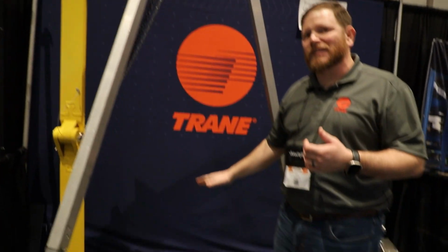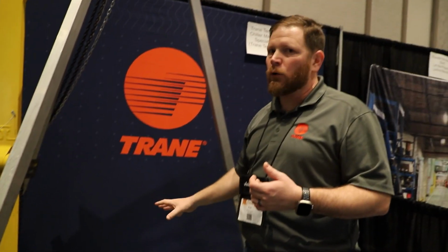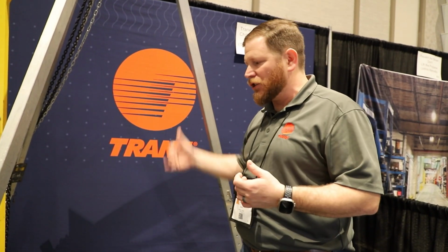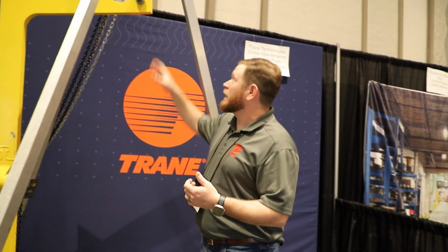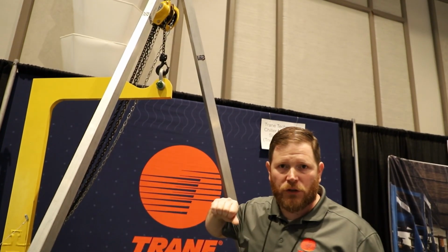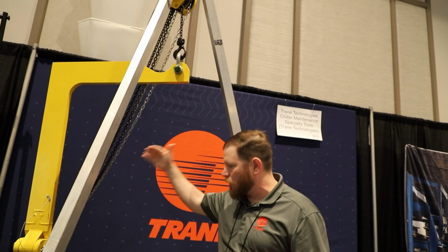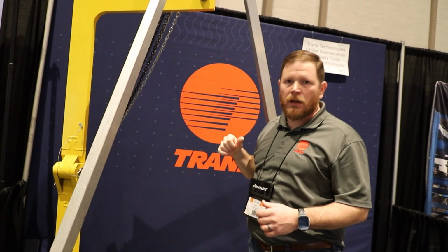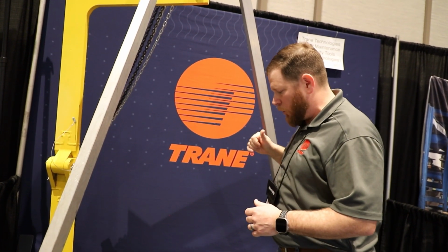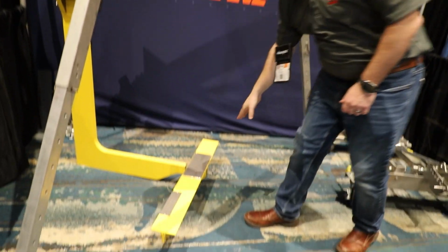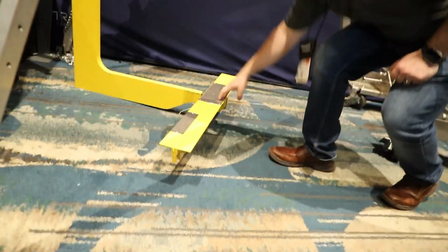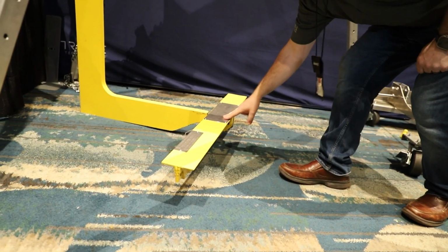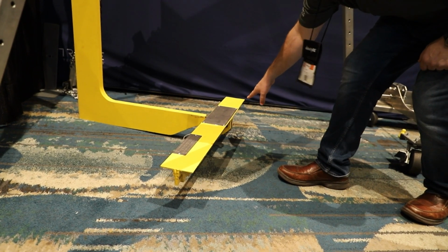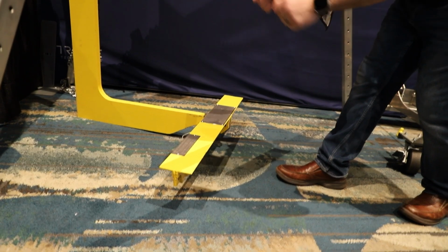This skyhook is designed so it can access the compressors in place, in their final resting spot in the chiller. If a technician goes to remove one, they can connect this to the crane they're utilizing on the job site. It reaches around our condenser coil section on the R-Series air-cooled chiller, and they can mount the compressor to this bottom rail. They have a plate telling them which lifting components to use depending on the compressor model, and they're able to hook directly in place.